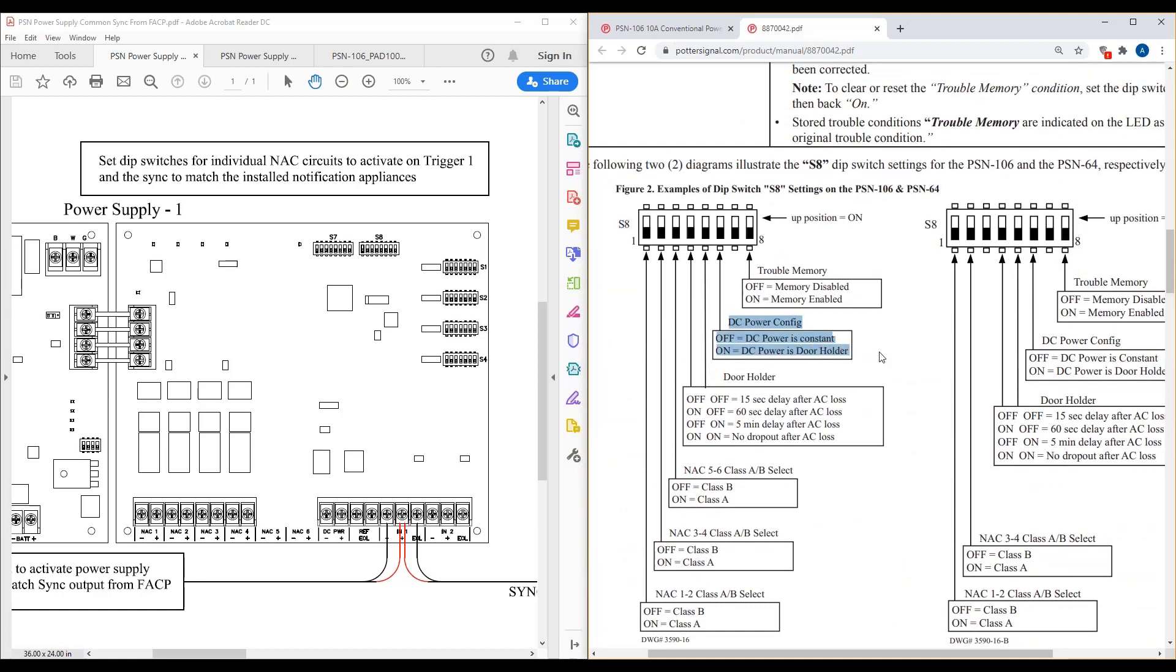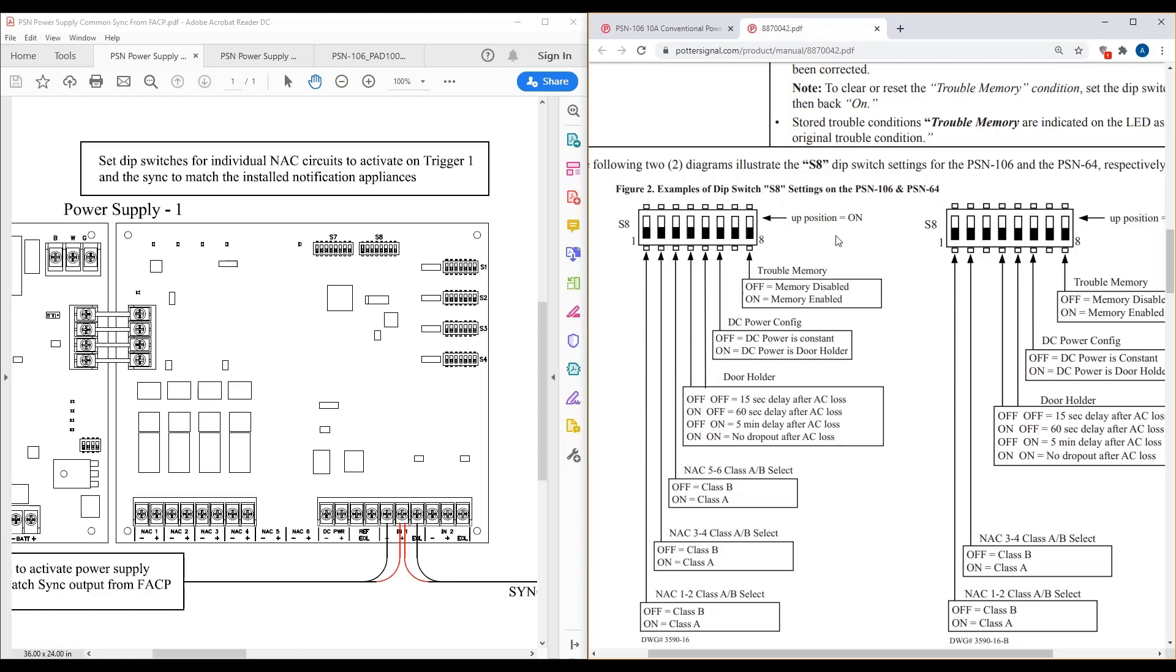While we're on this screen here, the other thing I'm going to talk about is this trouble memory. So one of the nice features that these conventional power supplies have is this trouble memory. If dip switch eight on bank S8 is in the up or on position and you get a trouble on this power supply and say that power supply goes back to normal status, the LED is still going to keep flashing rapidly for you. So that way, if it's an intermittent trouble, you can go to this power supply and determine, okay, it's NAC three. That's the one that's been going in and out of trouble. And to reset that, it's as simple as taking dip switch eight to the off position and putting it back to the on position. So I always highly suggest people turn the trouble memory on. I think it's an advantage for technicians out in the field when it comes to troubleshooting.